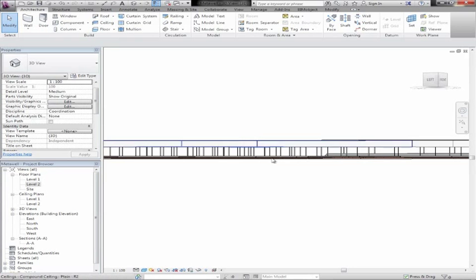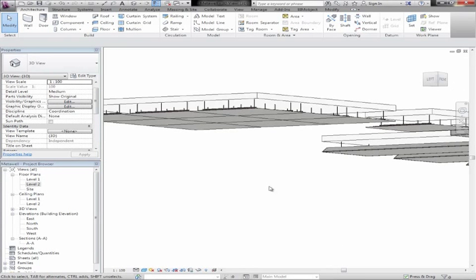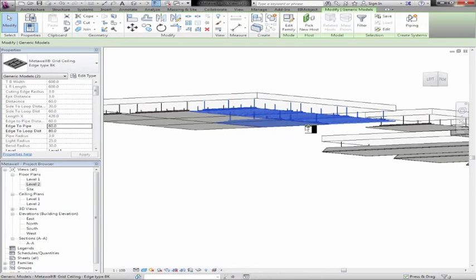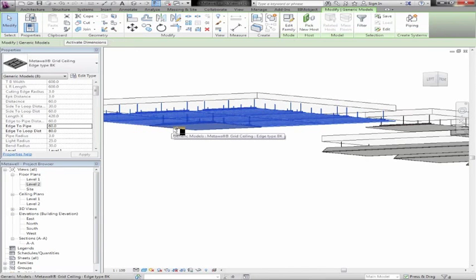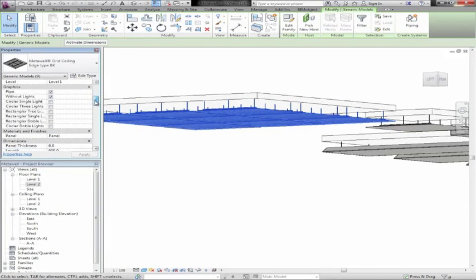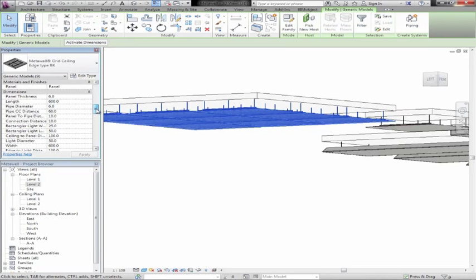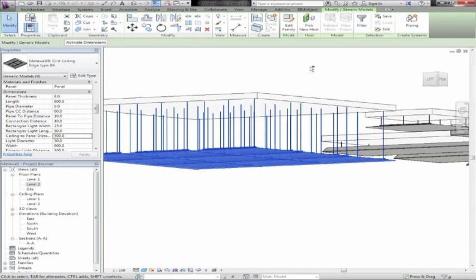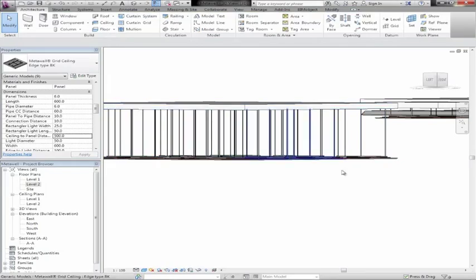We have a setting for distance from the ceiling. At the moment the default is 100mm. If we go ahead and mark these elements and change the ceiling to panel distance — for example to 500mm — we'll see that the panels drop down and are now 500mm from the underside of the ceiling.